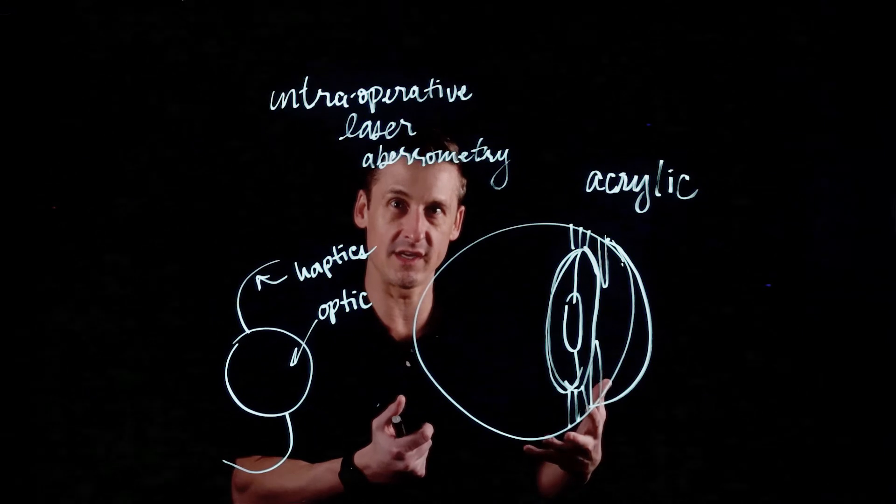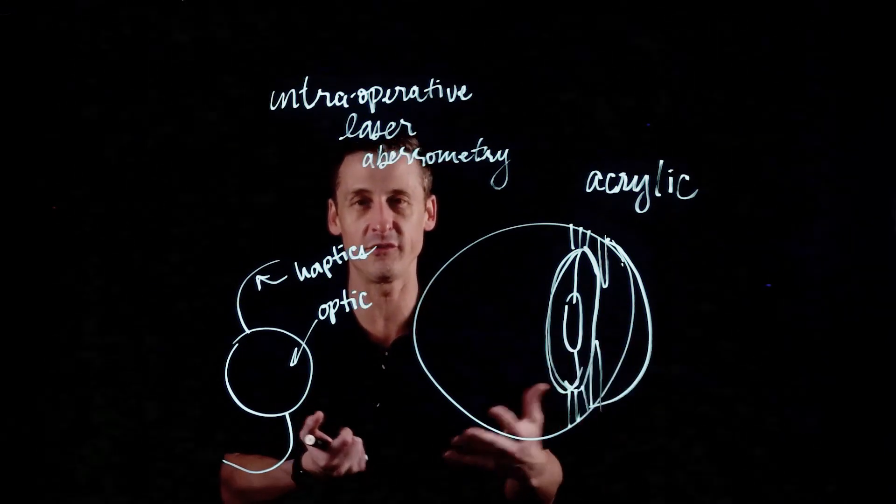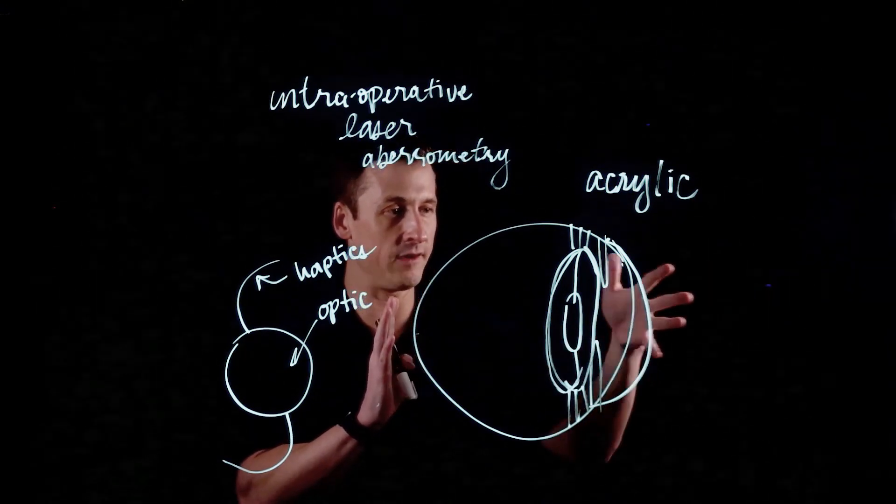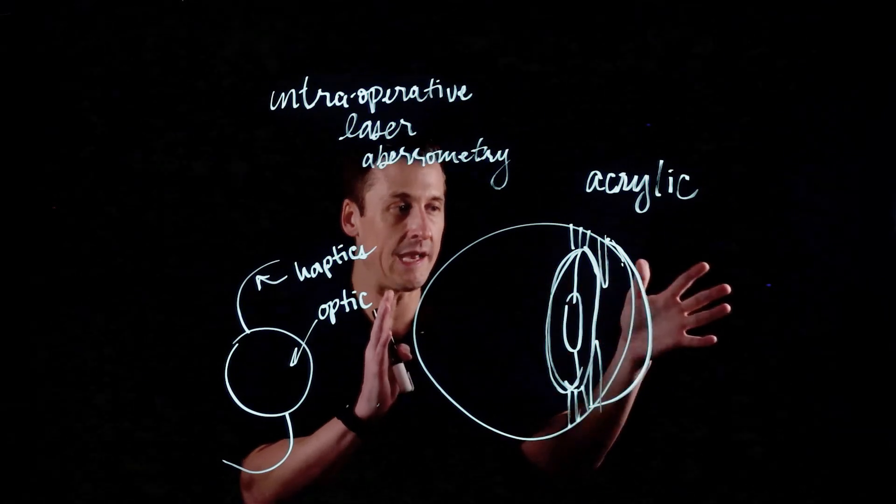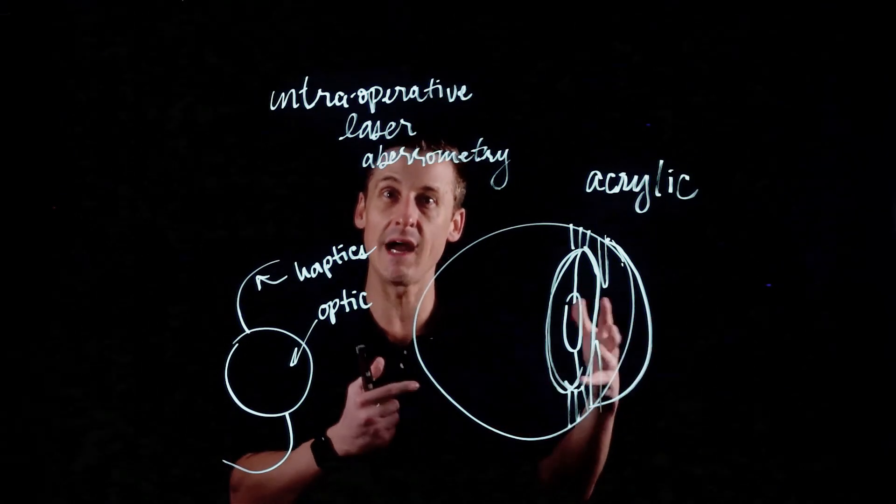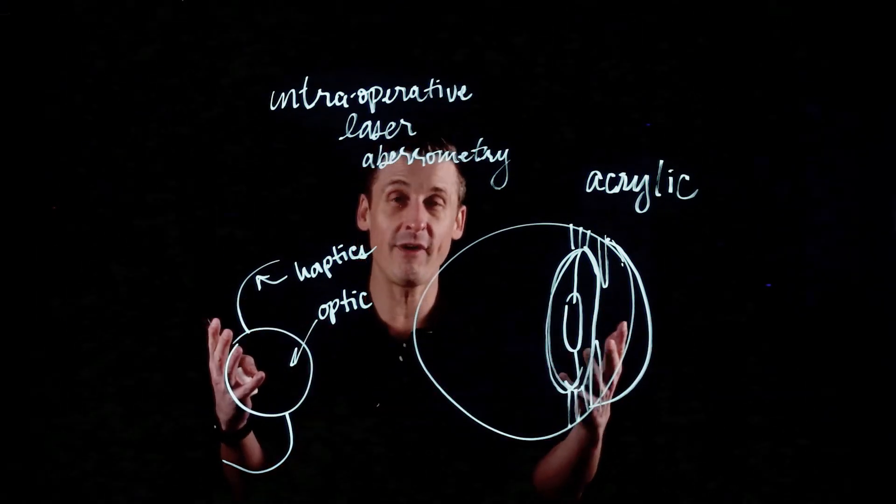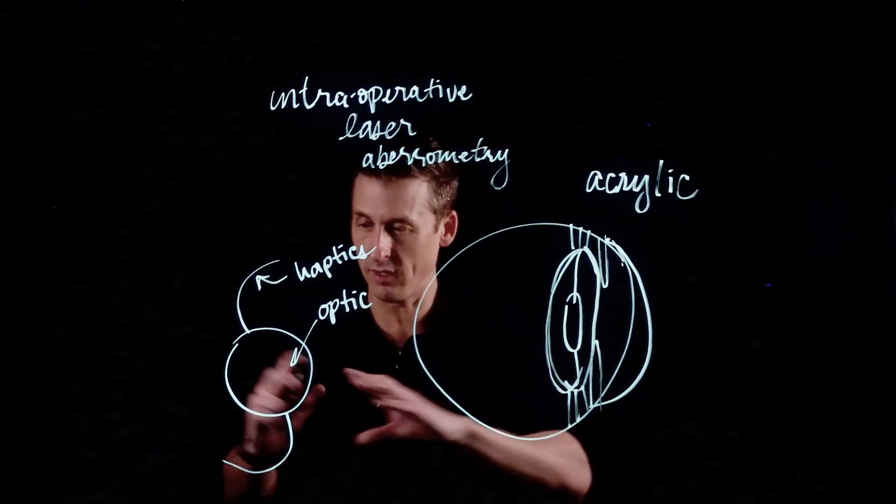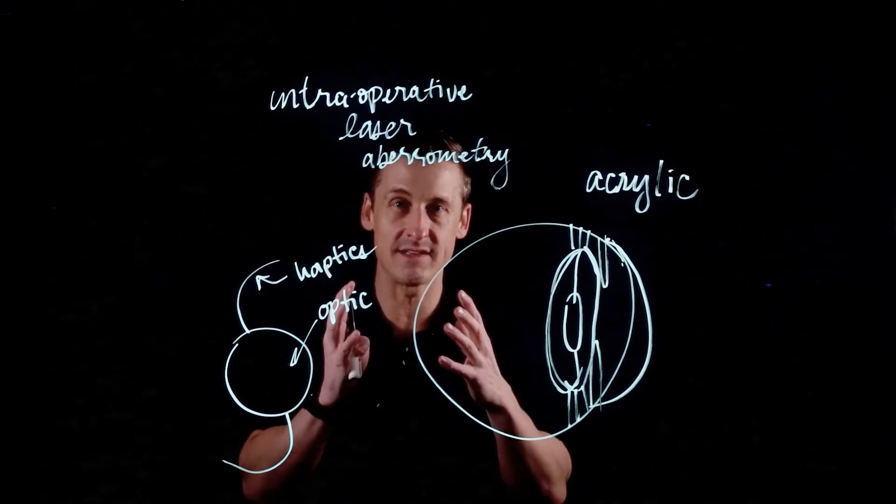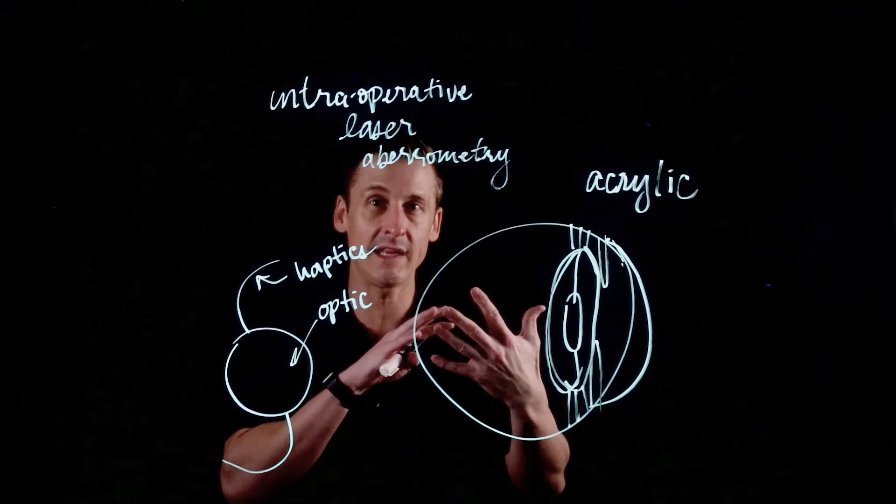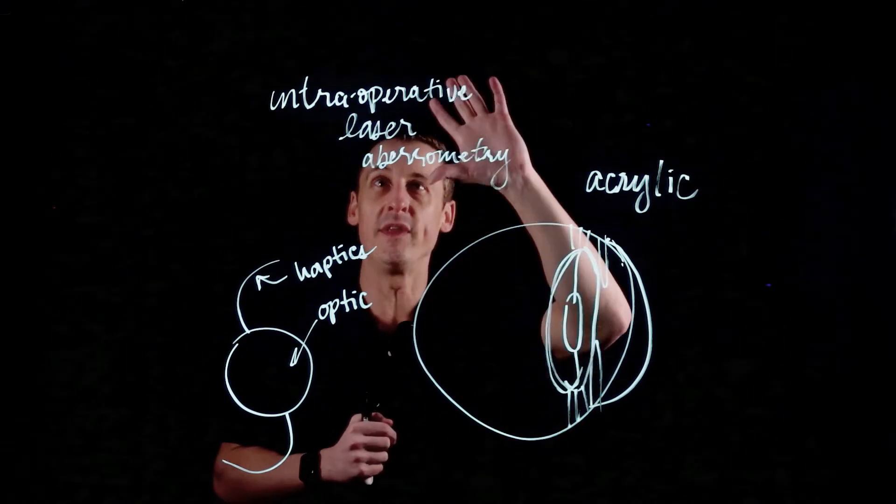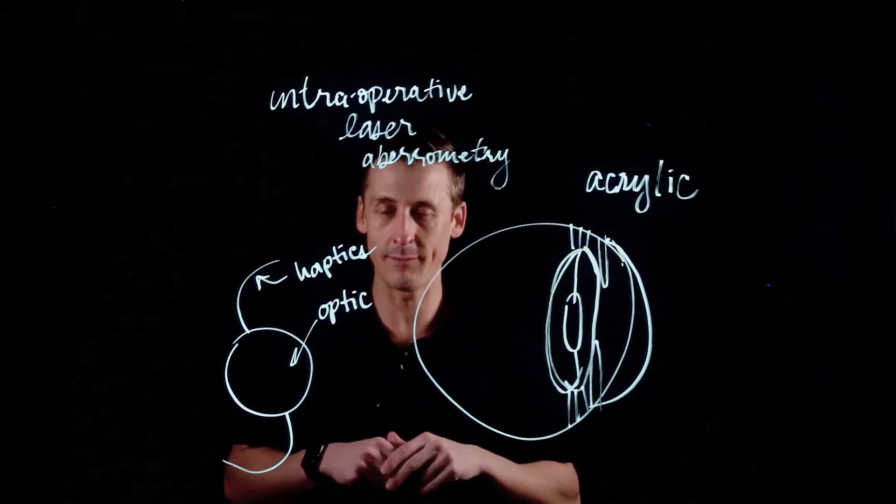So intraoperative laser aberrometry is a really long-winded way to say that with Star Trek-like technology, there's this part of the actual procedure itself where we're able to use a laser. Now it's an invisible laser, so you can't see it and neither can I, but what it does is it sends in this invisible grid pattern of laser light in the actual procedure and then measures it as it comes out to give us what the exact prescription is that this eye has. It's this thing that we never had available to us before. Calculating the power of this intraocular lens was always the product of coming up with very exact dimensions of the curvature of the eye and the length of the eye and the proportions of the eye, and then doing math to figure out what power lens do you need. With intraoperative laser aberrometry that's come along now just in the last decade...